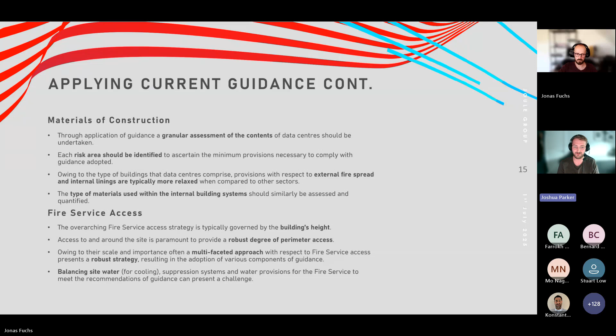That multi-story aspect, given the floor height, can push us over the thresholds where perimeter access is no longer acceptable, but providing it even in those conditions enables this multifaceted approach to be developed. The balancing of water is always an incredibly difficult challenge. Many data center cooling systems rely on that water and often run to destruction, so maintaining cooling for building services not undergoing fire conditions, while also delivering the necessary water for the fire service, is always a balanced argument between all parties, including mechanical engineers, to achieve each objective and align with the 9990 requirements.